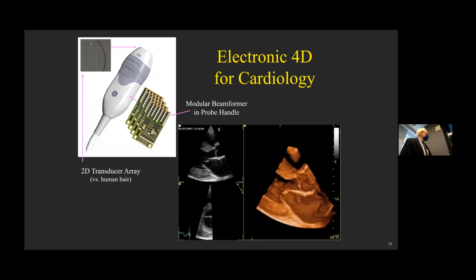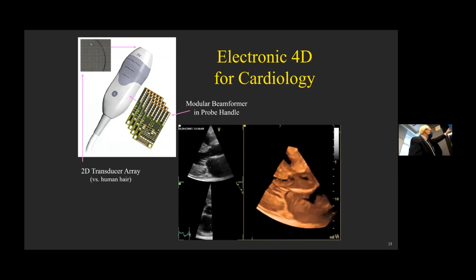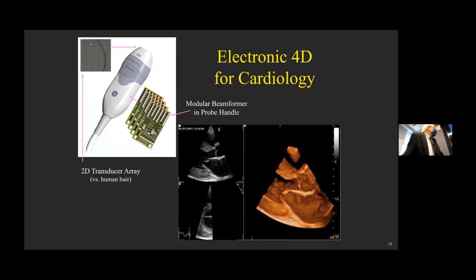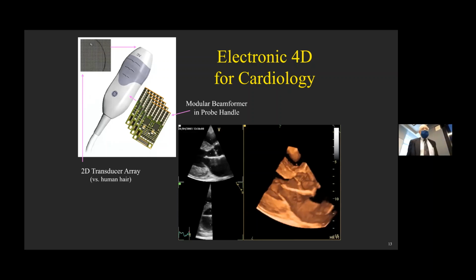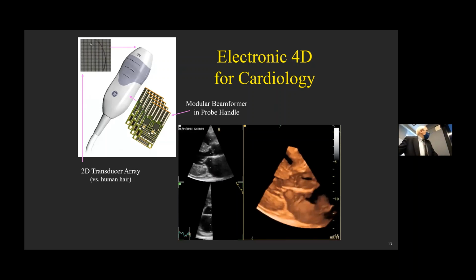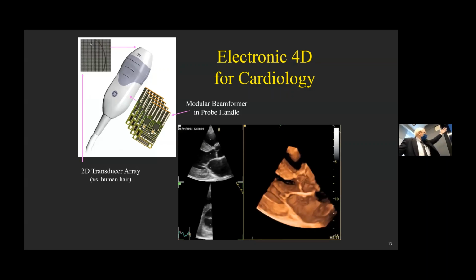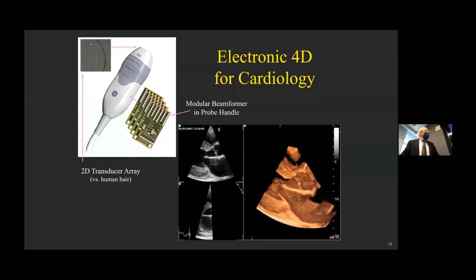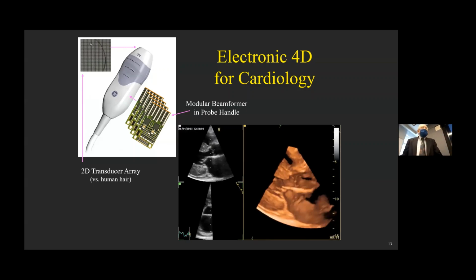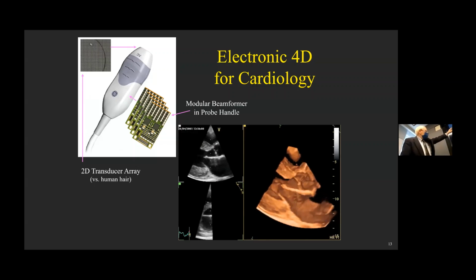cardiology probe. For scale over here on the left-hand side, I show the transducer array. If you want to understand what the appropriate scale here is, that curved thing is a strand of my hair. I measured it, it's 80 microns in diameter. And you can contrast that, there's that little thing sitting up on the top. That's one element of the transducer array that we picked off from the side that's not in the image there. And so you can see that it's maybe of order 200 microns on the side, maybe, and 400 or 500 microns thick. A bunch of stuff there. That's at the very front end. Then there's a bunch of electronics in here.